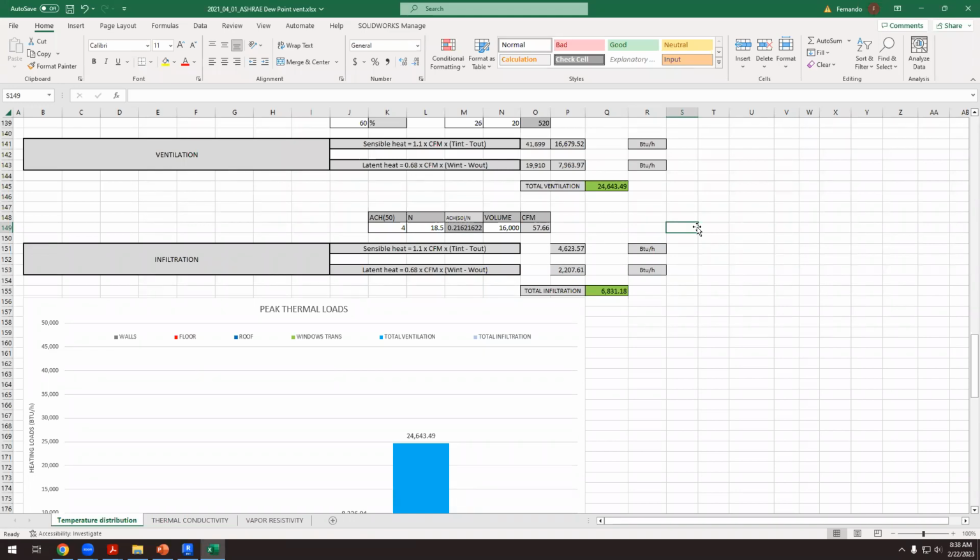Okay, so if we have this, when the difference between the outdoor pressure, this is the atmospheric pressure, it's the pressure that we have outdoors, and the indoor pressure, we are extracting air. So if we are extracting air, we are reducing the indoor pressure. So at the point in which we have this blower door test, we have a meter, and we say, okay, so that's 50 pascals. When we have 50 pascals, we have to look at the infiltration rate.